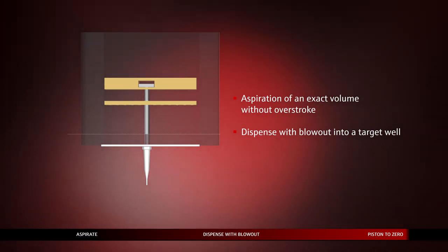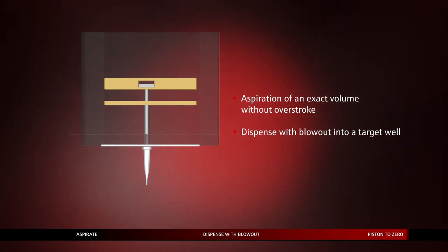To summarize, forward pipetting consists of aspirating an exact volume without overstroke from a source well and dispensing with blowout into a target well.